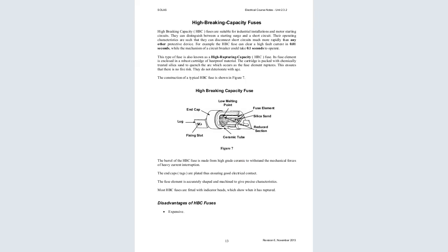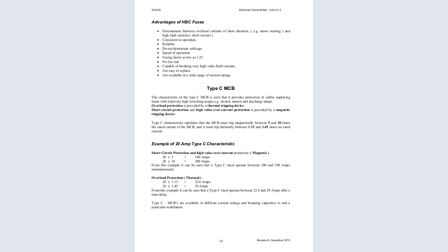The barrel of the HBC fuse is made from high-grade ceramic to withstand the mechanical forces of heavy current interruption. The end caps, or the tags, are plates that ensure good electrical contact. The fuse element is accurately shaped and machined to give precise characteristics. Most HBC fuses are fitted with indicator beads which show when it has ruptured. The disadvantage is that it is very expensive. The advantages are that it discriminates between overload currents of short duration, for example motor starting, and high fault currents, that is short circuits. It is also consistent in operation. It is reliable.